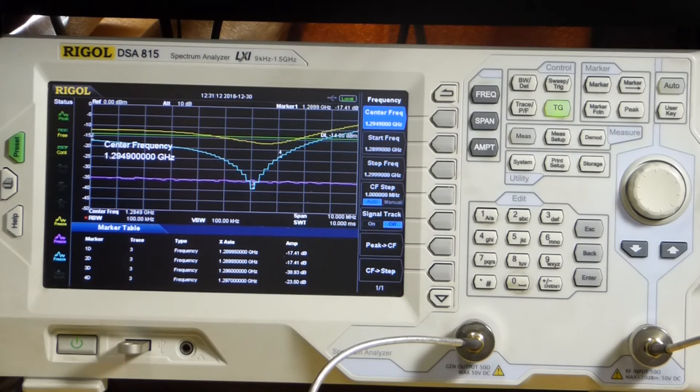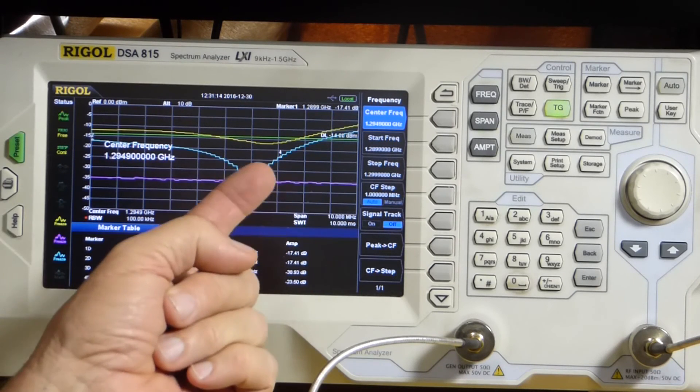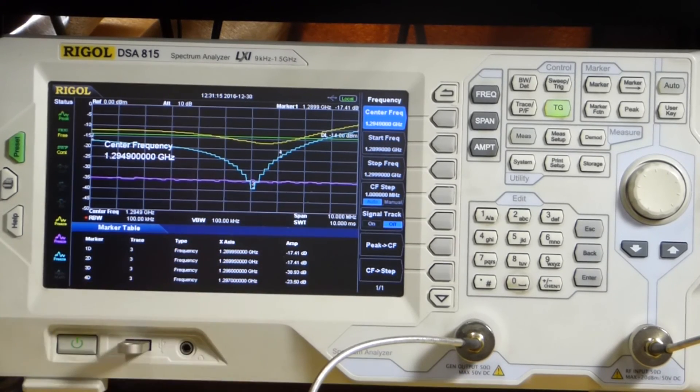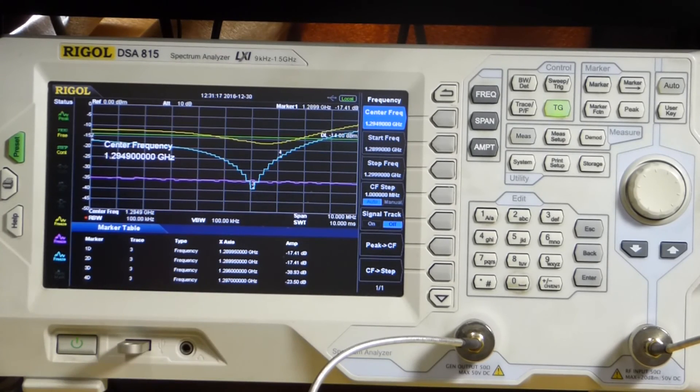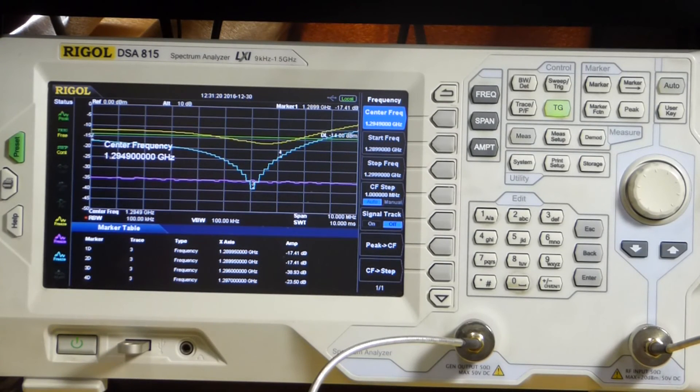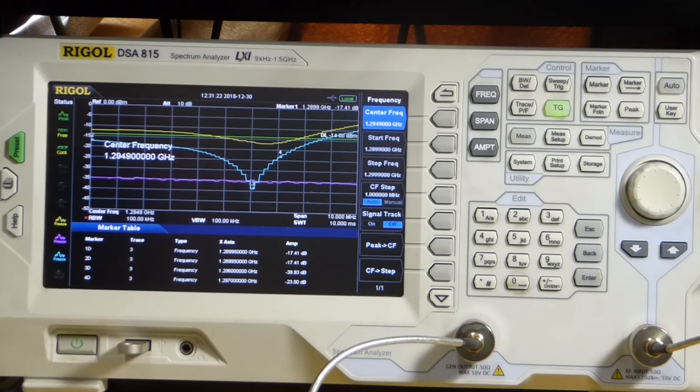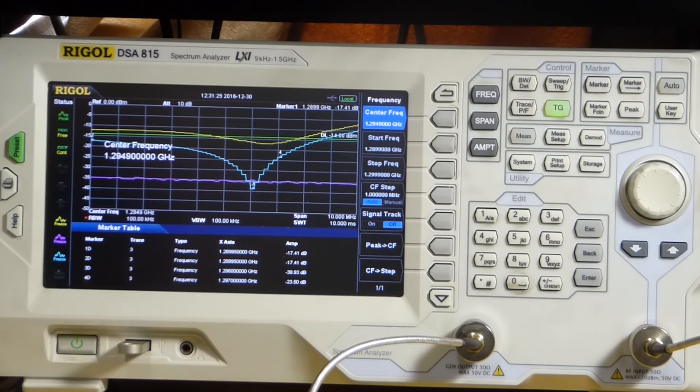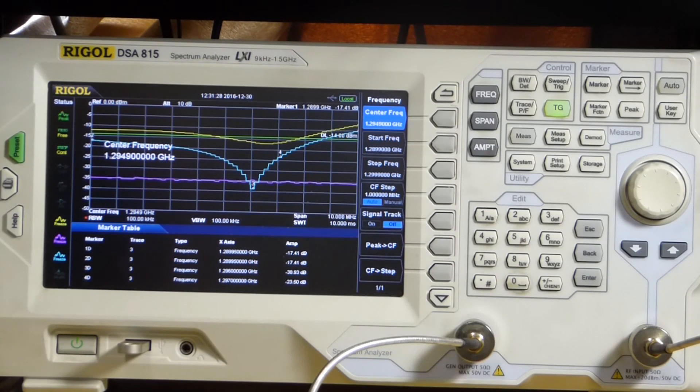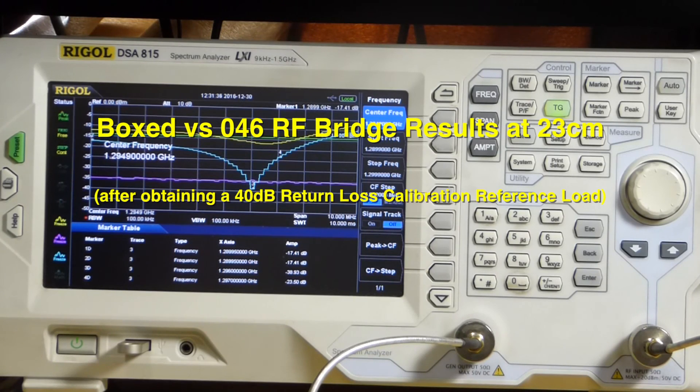So that's just a feature of this Rigol Spectrum Analyzer you can use if you need to. You can take one wide pass at the thing and then narrow it down and narrow it down for two different pictures, or three different pictures, as you wish to do. So that's a feature some of you may have discovered, and some of you may not have discovered. And I thought I'd just show it in this short video.